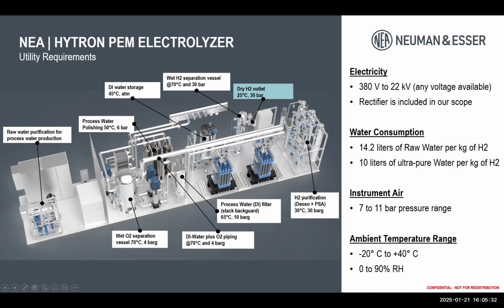In terms of utility requirements, I get this question from clients very often: what should I provide to the stack? I decided to put a slide summarizing the utility requirements. The system can pretty much handle any voltage available at site. The transformer is optional in our scope. You don't need to buy it from Neuman & Esser, but the rectifier is always in our scope. If the utility company can provide a transformer, that's fine. The rectifier is going to regulate the voltage and current going into the stacks. Since it's part of the stack capacity control, we prefer to provide a rectifier.